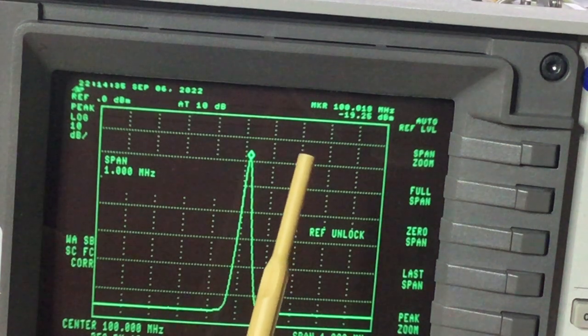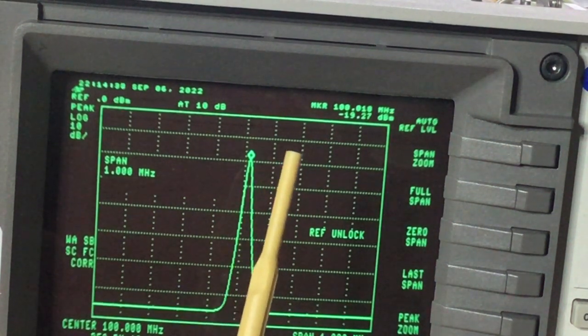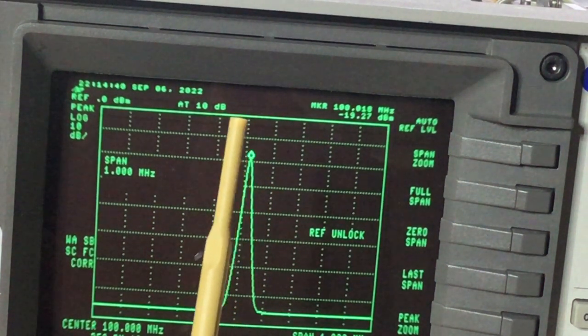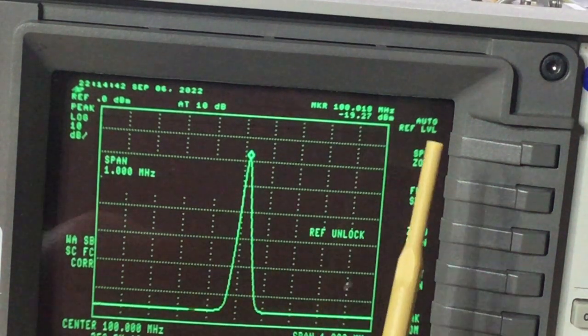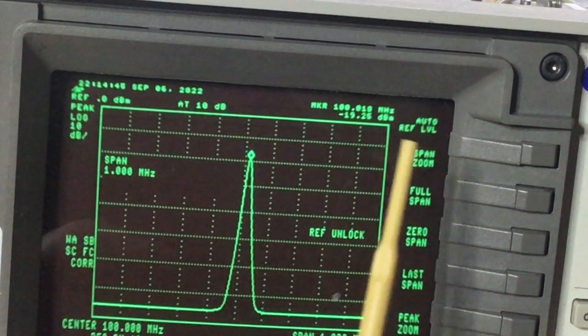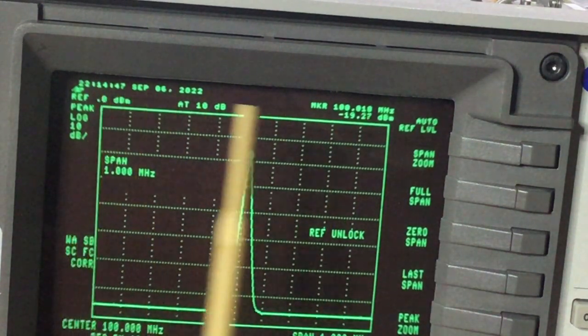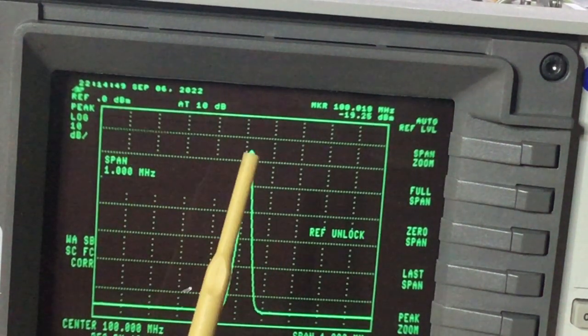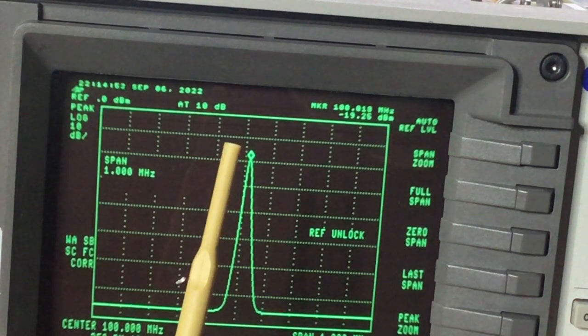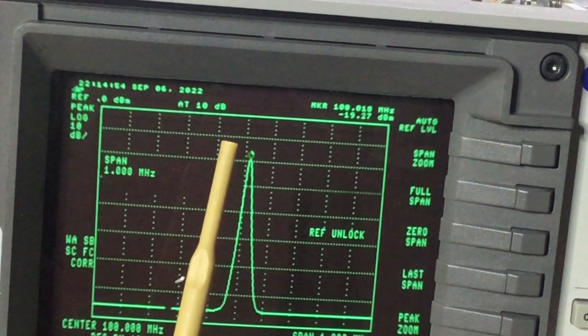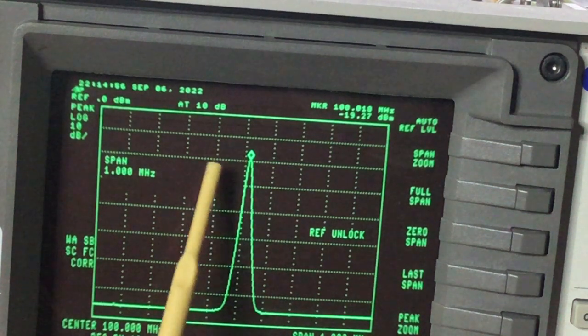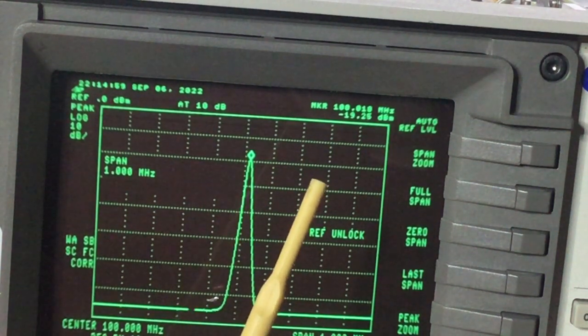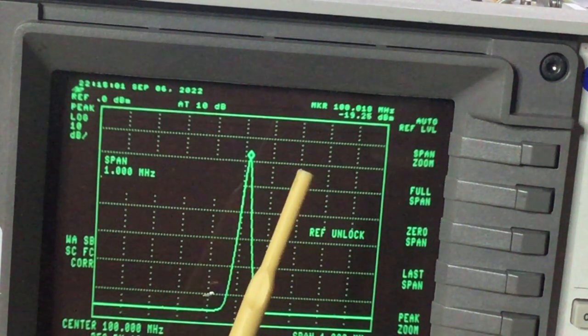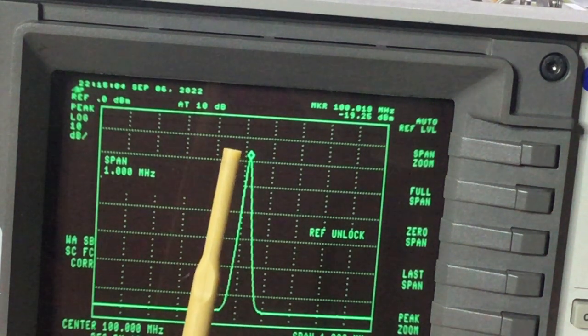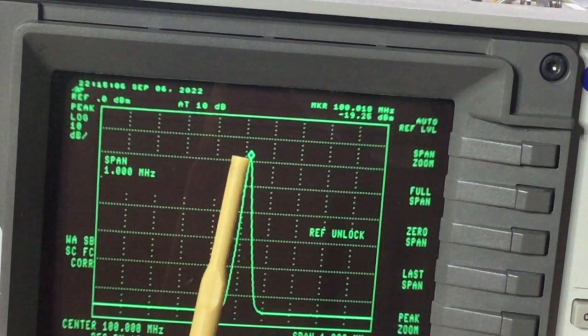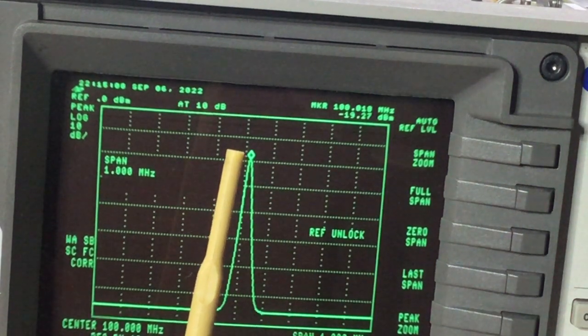With such small incremental changes in the 10 megahertz reference oscillator, the 10 megs only has to alter just slightly for a huge fundamental change in the 600 megahertz and hence 300 megahertz calibration signal. And it could be that the DAC values, if you remember earlier when we tried in the service maintenance menu of the instrument to make the DAC value change the frequency of a calibrator signal, it didn't do that. And I think it's because it had gone too far off frequency.